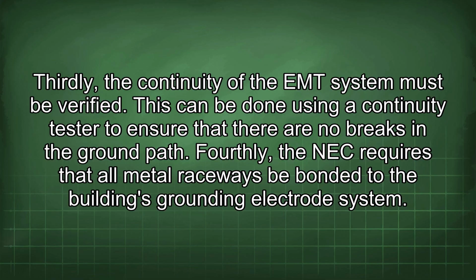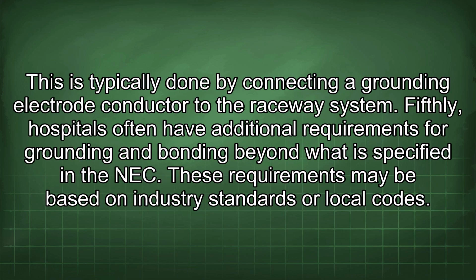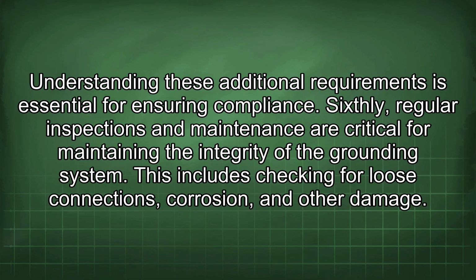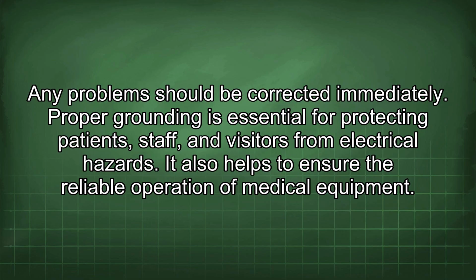Fourthly, the NEC requires that all metal raceways be bonded to the building's grounding electrode system. This is typically done by connecting a grounding electrode conductor to the raceway system. Fifthly, hospitals often have additional requirements for grounding and bonding beyond what is specified in the NEC. These requirements may be based on industry standards or local codes. Understanding these additional requirements is essential for ensuring compliance. Sixthly, regular inspections and maintenance are critical for maintaining the integrity of the grounding system. This includes checking for loose connections, corrosion, and other damage. Any problems should be corrected immediately.